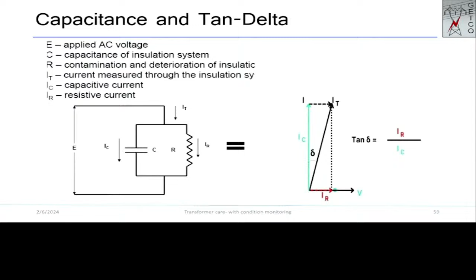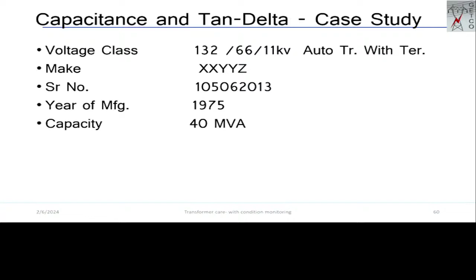Okay, and so this aluminum foil is removed, re-insulation provided, and the transformer put back into service. So there is a saving of approximately 1.55 crores. This is the single case study of DGA. The second case study is of capacitance and tan delta.